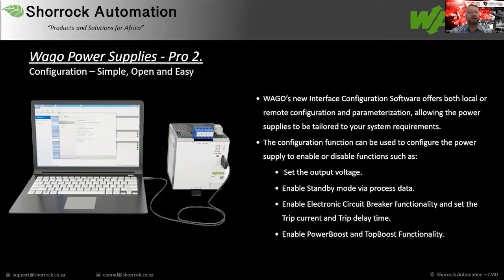We can then limit the current on this device to 35 amps and put a trip delay on that as well. In addition, electronic circuit breakers are really important for applications where you use 24 volt DC. A common mistake we find out in the industry as well is customers using normal DIN rail circuit breakers that are not rated for DC applications. Simple breakers, that's a 2 amp circuit breaker with a 250 volts AC rating, basically means that it needs a short circuit of about 8 seconds before that circuit breaker will trip.